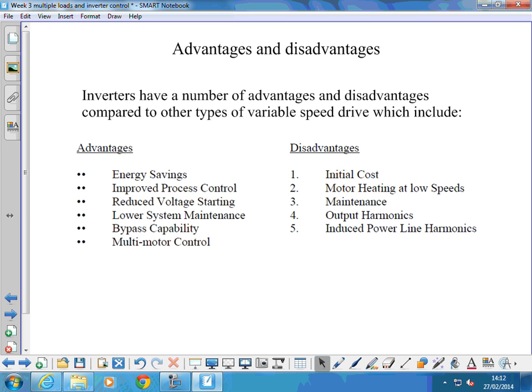The disadvantages are the initial cost of an inverter. Whilst they might be getting cheaper, chances are they cost more than a direct online starter. At low speeds, you get excess motor heating. Again, we'll look at that a little bit more closely in a minute. There's the maintenance issue of the inverter, complex electronics. So your average maintenance engineer probably isn't going to know how to delve into the inverter and repair it if it breaks down.